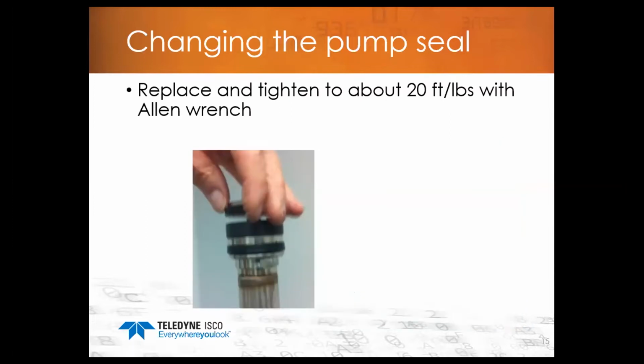Then go ahead and, with your seal back on the retainer, you'll thread that back on to the piston base. Most customers, a majority, are not going to have a torque wrench. If you do, we torque it to 20 foot-pounds. Basically, once you get the retainer tightened onto the piston, I would suggest just pretty much as tight as you can get it with the Allen wrench.